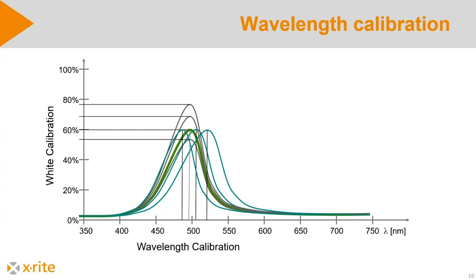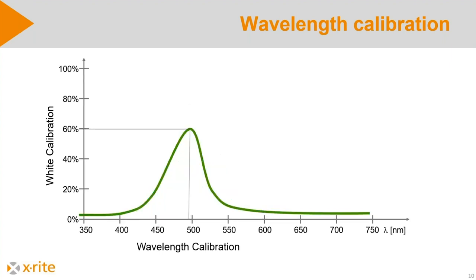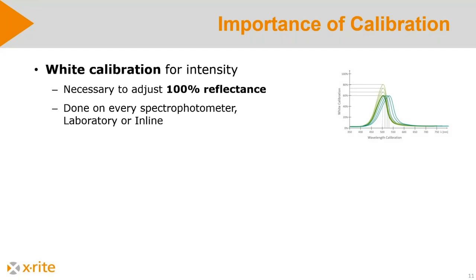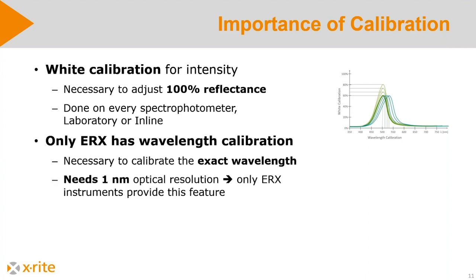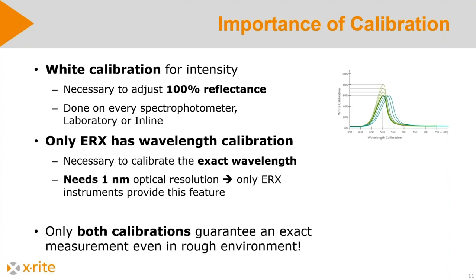And the ERX instruments are the only family which is doing this. This is the reason why this instrument is very stable in the short term, in the long term, and even after service. So you have exactly the same values. This is what we want to measure, and this is what we get after the calibration. Altogether, if we do the white calibration, we have to adjust the 100% reflectance, which is done at every instrument, but also the wavelength calibration, which is done only with the ERX 145 instrument, to have a very stable and accurate measurement. Accurate not only for this one measurement head we have on the line, but also for the measurement head we have on the machine. Only both calibrations can guarantee a really good measurement on the machine and in the laboratory.